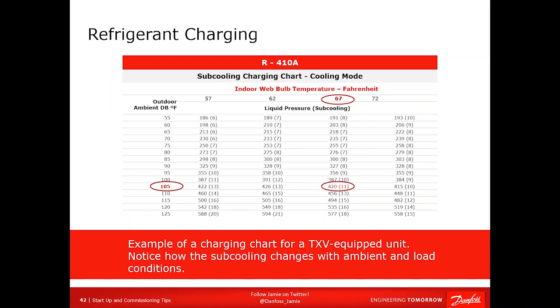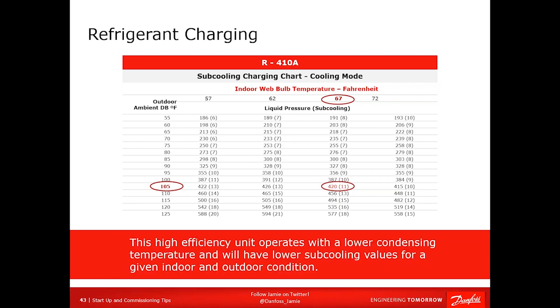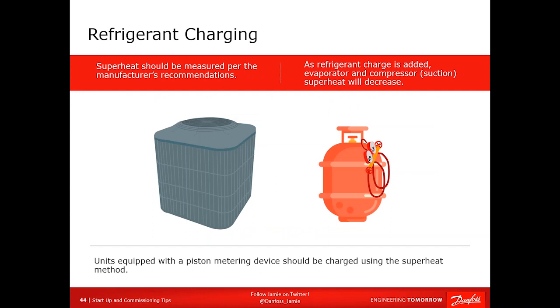So here you have an outdoor temperature, an indoor wet bulb. You're going to charge this particular system to a window of 420 psi and 11 degrees of subcooling. If this was a high efficiency system, you could easily have that 420 number drop to 390 and 11 degrees drop to 8. So this is not a universal chart. It is only for this particular piece of equipment. Always refer to the manufacturer, because if you have a high efficiency system, then you're going to need to have the correct charge. Otherwise, you're never going to get that efficiency out of it.